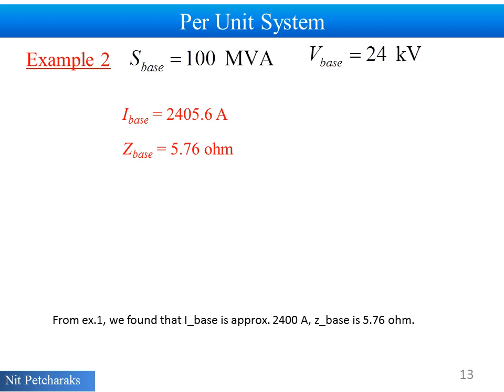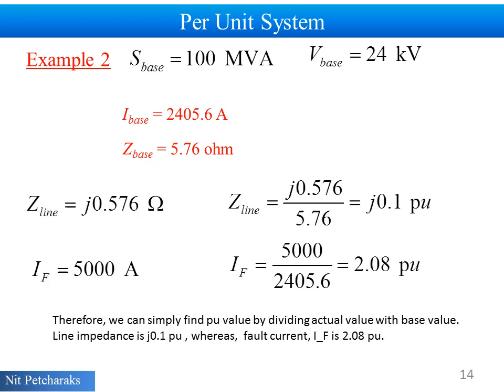From example 1, we found that base current is approximately 2400 amperes. Base impedance is 5.76 ohm. Therefore, we can simply find per unit value by dividing actual value with base value. Line impedance is J0.1 per unit. Whereas, fault current IF is 2.08 per unit.